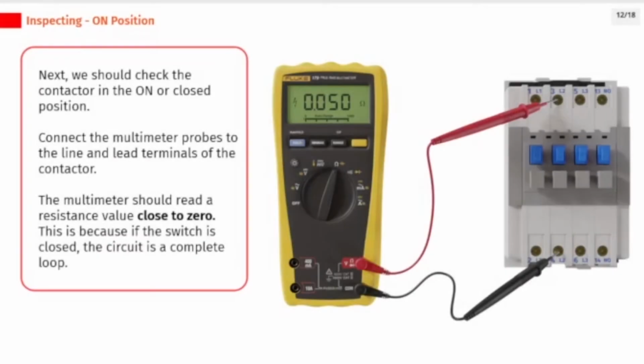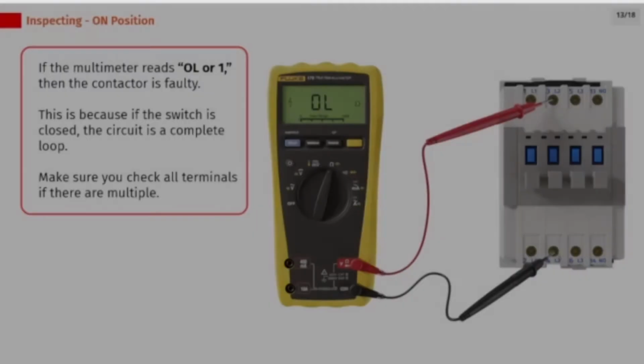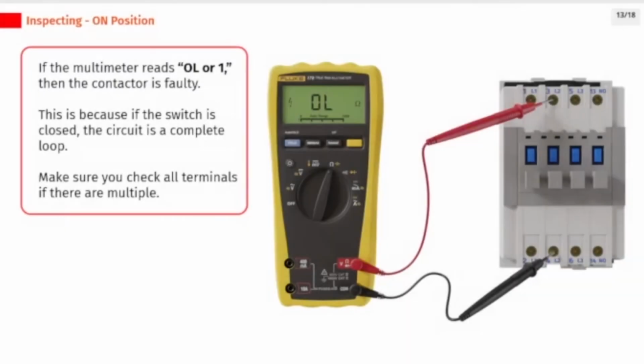Next, we should check the contactor in the on or closed position. Connect the multimeter probes to the line and lead terminals of the contactor. The multimeter should read a resistance value close to 0. This is because if the switch is closed, the circuit is a complete loop. If the multimeter reads OL or 1, then the contactor is faulty. Make sure you check all terminals if there are multiple.